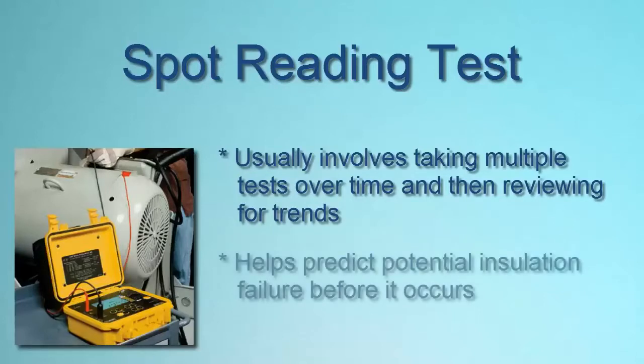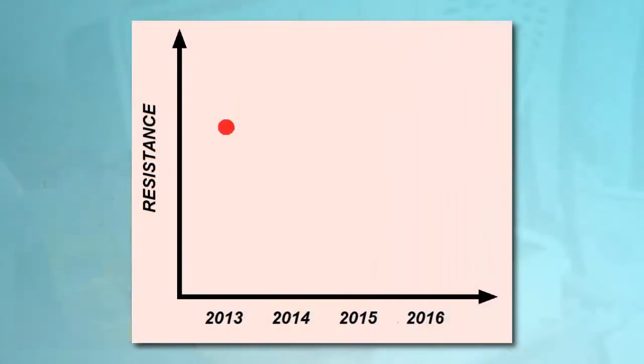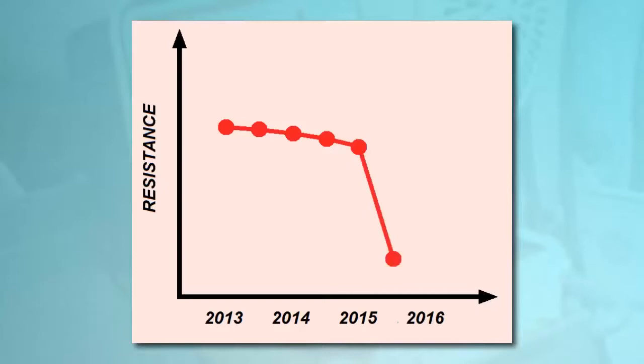This comparison can help predict a potential insulation failure in time to take corrective action. For example, suppose you perform a spot test every six months. Plotting the results on a graph, you observe a slow and gradual downward trend, as would be expected by the normal aging of insulation. However, if your latest measurement reveals a sudden drop in resistance, this is likely an indication that the insulation has begun to deteriorate at an accelerated rate. To address this, you can schedule downtime for the system and take appropriate measures such as cleaning, upgrading, or replacing the insulation.